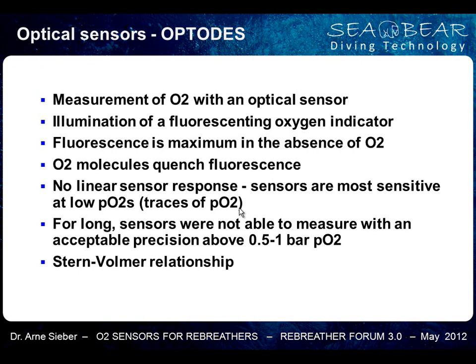Optical sensors. This is also a different type of sensor technology that might come. It works like this: you have some kind of layer, and you illuminate this layer with a light, and you get a fluorescence. Depending on how much oxygen you have in the gas in front of that layer, you have less fluorescence. So the higher the oxygen level, the less fluorescence you have.